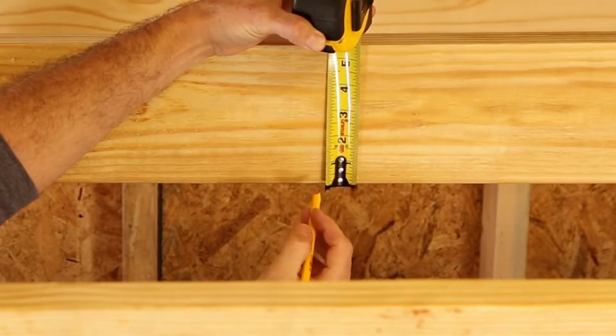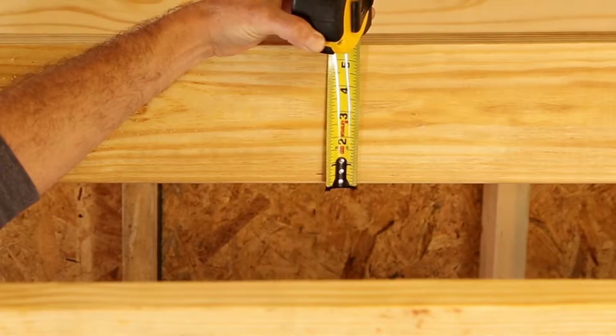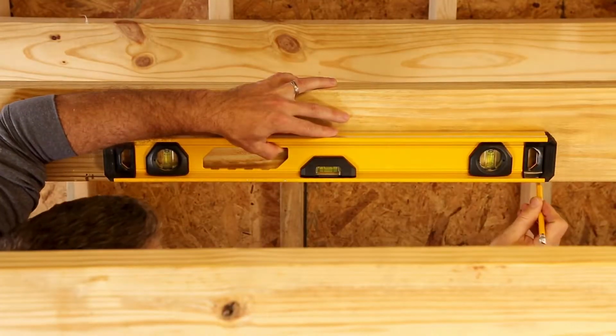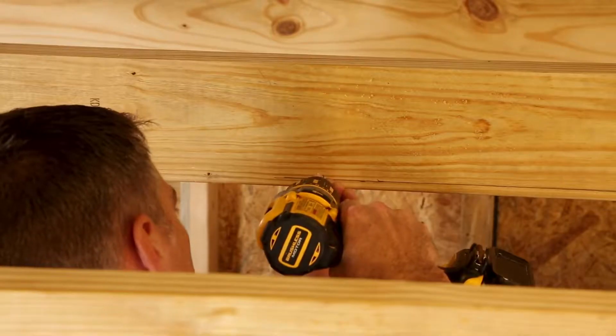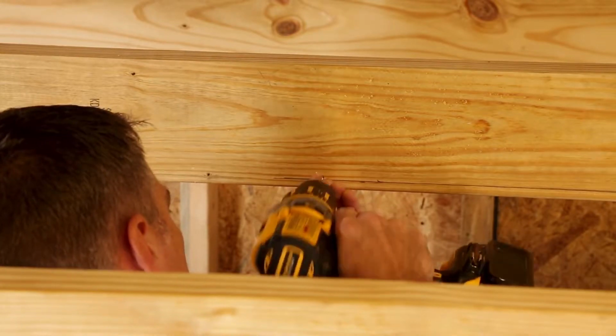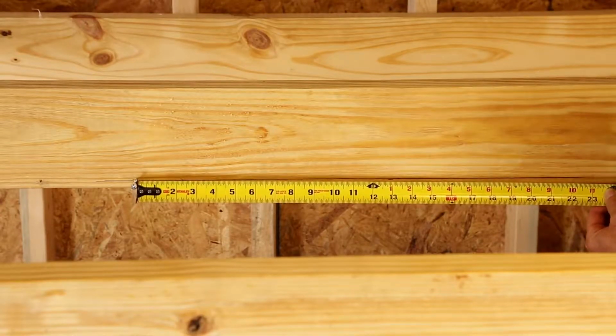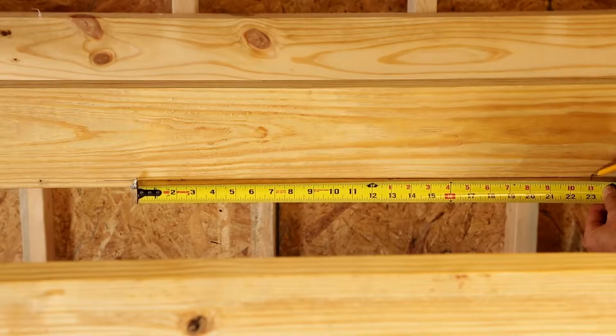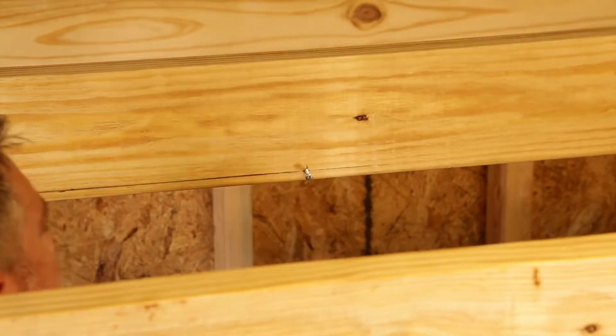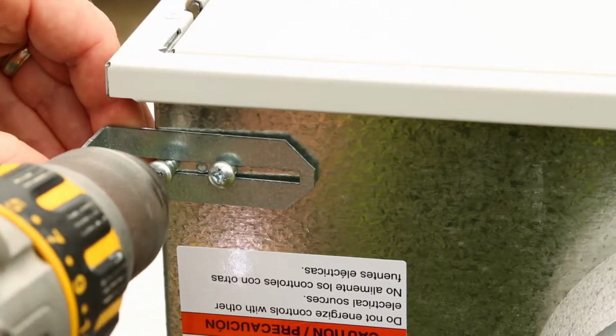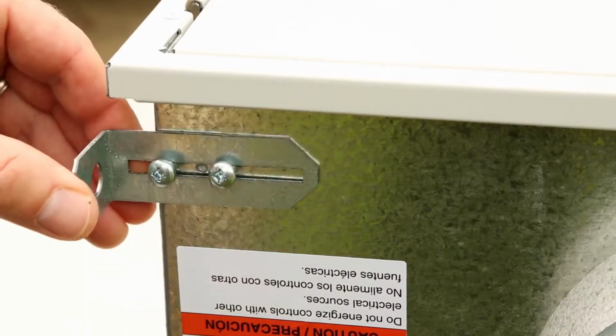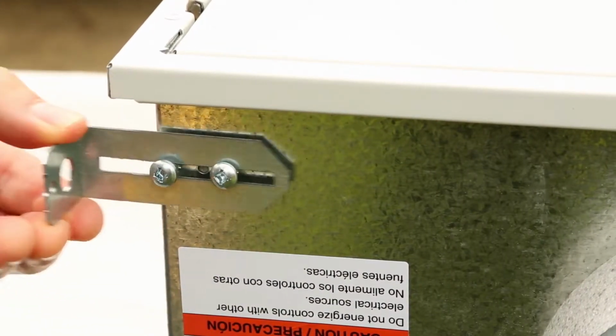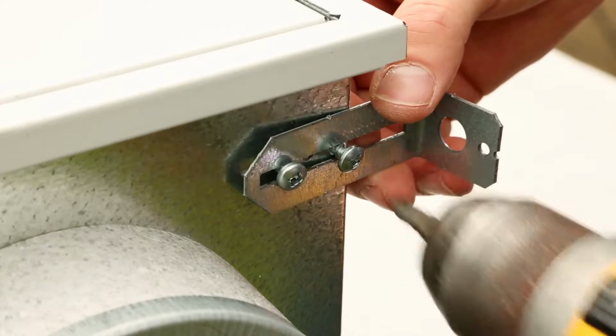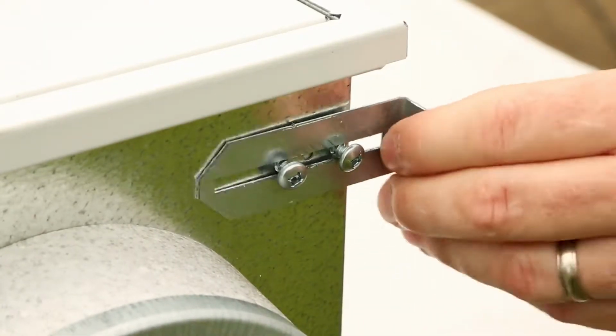To install the unit overlapping the ceiling material, trace a level line on both trusses 1/2 inch from the bottom of the trusses. On the level line on one truss, screw two number 8 by 1.5 inch screws halfway into the truss, leaving 23 inches between the screws. Mount 2 brackets to each end of the unit, using two number 10 by 5/8 inch screws per bracket. Only screw the screws in halfway to allow the brackets to slide for adjustment between the trusses.